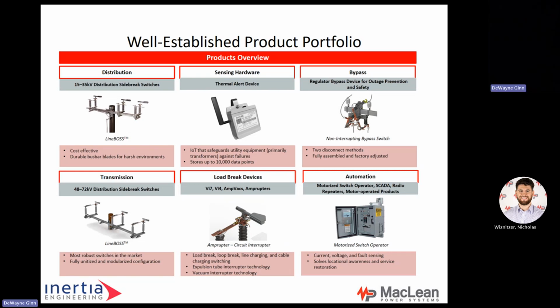Sensing hardware: we have a product called Thermal Alert Device, or TAD, which allows you to sense the transformer and see if it's going to go into a runaway situation. We can talk a little bit more about that later in the presentation. A voltage regulator bypass switch allows you to bypass the voltage regulator without having to take an outage. This has been around for over 50 years, and it's a very safe and easy way to take a regulator offline. Load break devices: we manufacture our low break devices in-house from 15 kV, which is 600 and 1200 amp, all the way to 2000 amps. Automation products allow you to have SCADA ready equipment, and you can operate motor operators from your SCADA control house.